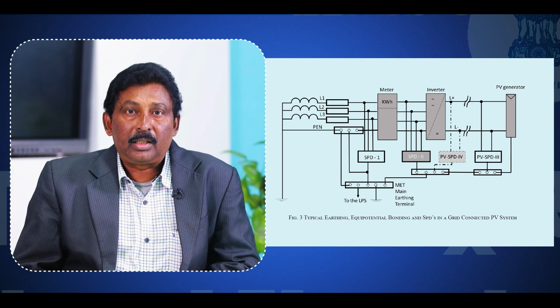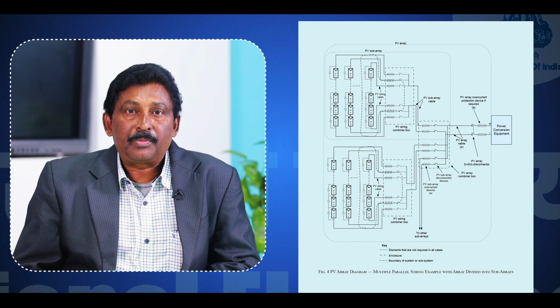Solar installation has a lot of DC system in which general protective system adopted for AC system may not work directly. Special measures are necessary for fault protection and shock protective measures. This part covers essential requirements for solar PV installation, including module, string and array, inverter, controller and balance of system in one consolidated place, covering design, installation, safety and quality requirements of PV installations. It covers requirements of wiring, protection, surge protective device and earthing of rooftop and industrial structure, and covers all aspects in rooftop category as well as in utility scale.